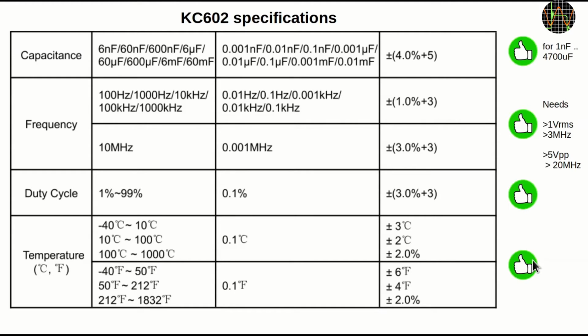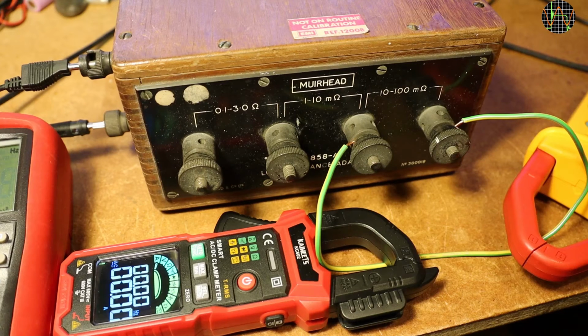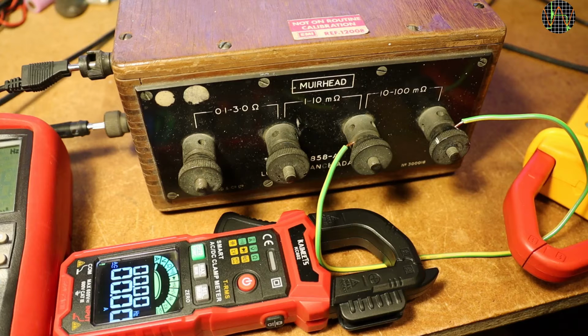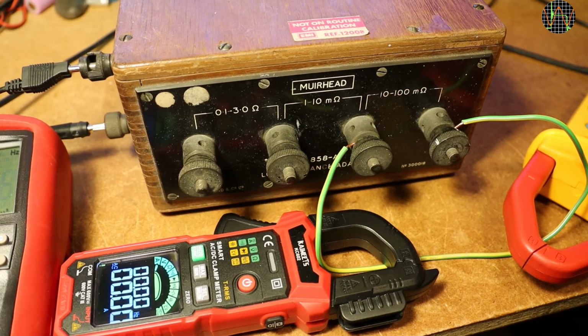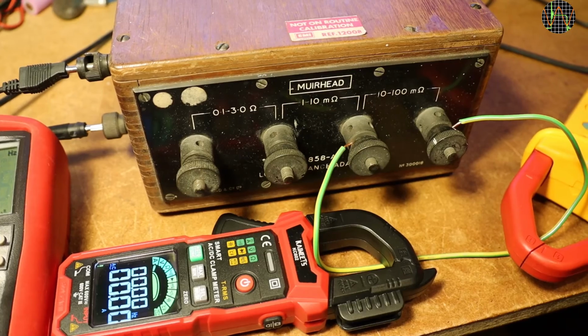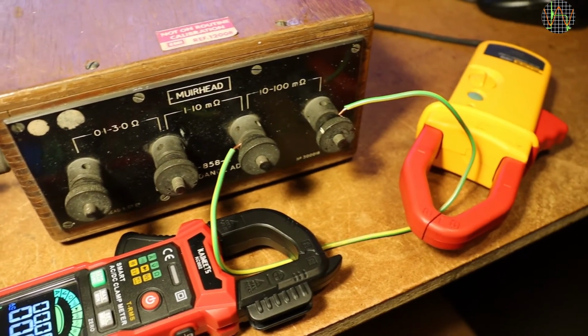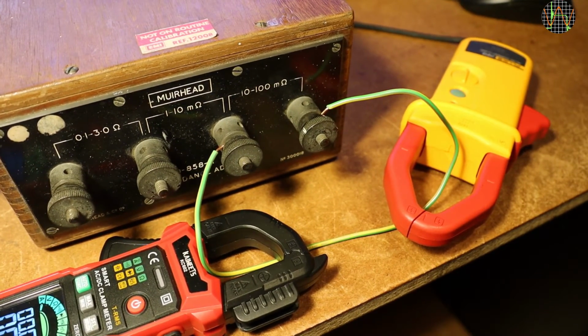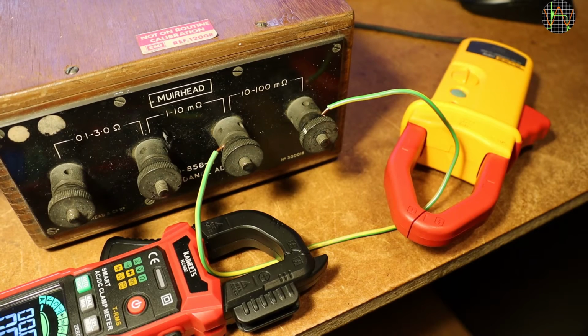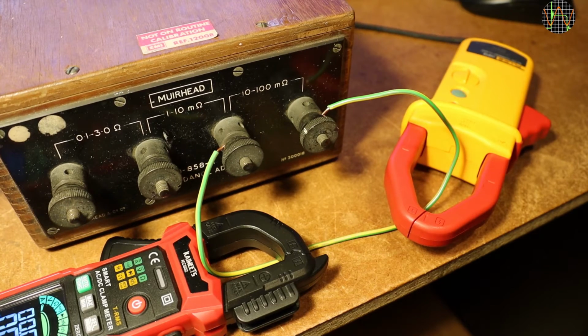With that out of the way, a quick note on how I tested some of the more unusual stuff. For AC currents beyond 10 amps, I used this setup. This old low impedance adapter is basically a transformer with massive copper bands on the secondary. Basically you trade low currents and tens of volts on the primary side for fractions of volts but tens of amps on the secondary. I shorted the secondary terminals with a copper wire which goes through the KC602 clamp and the clamp of my Fluke i1010 adapter.